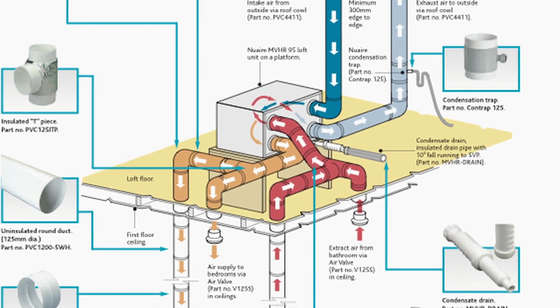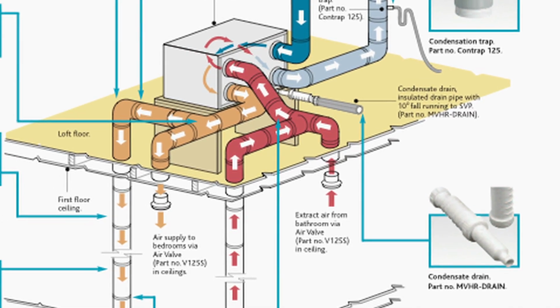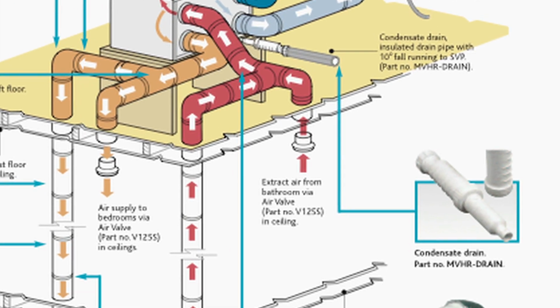Nuaire's heat recovery systems are currently in the region of 95% efficient. A 95% efficient heat exchange block can produce a substantial amount of condensation. It's important that this condensation is taken away from the unit to prevent damage to the unit and to the building. One very important aspect of it is the use of a trap.